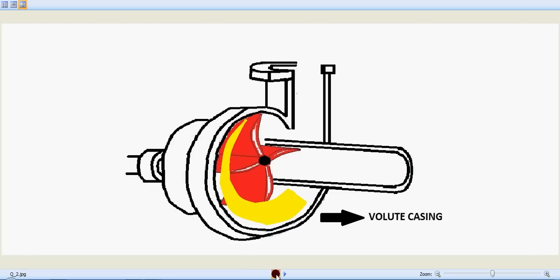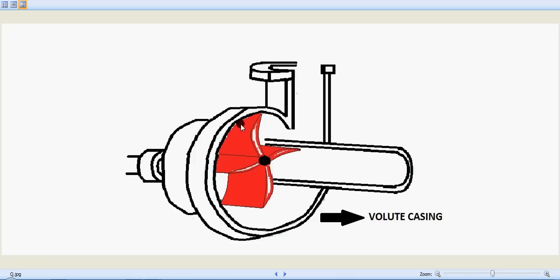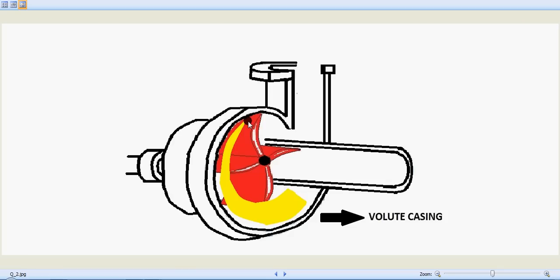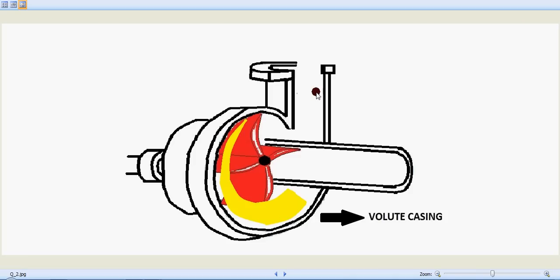As you can see at the top we have less area gap between the casing and the impeller, but as it comes down the area increases as shown here in the yellow shade. So what happens is that at the top the velocity of the oil will be much higher and the pressure will be less, but as it comes down and the area increases, velocity gradually decreases and thereby the pressure increases so we'll get a pressured discharge over here.